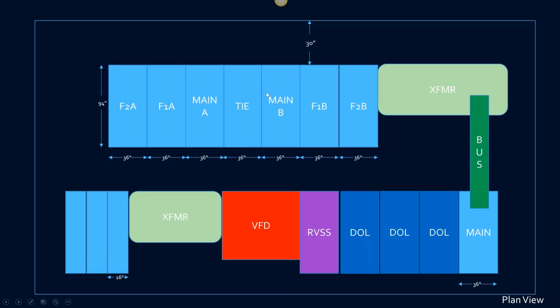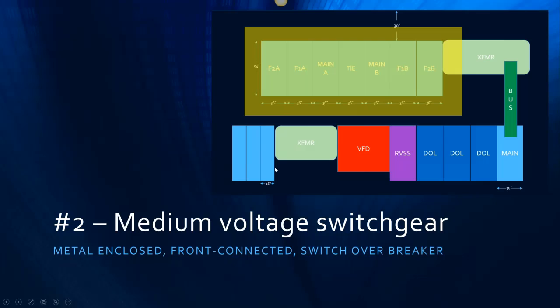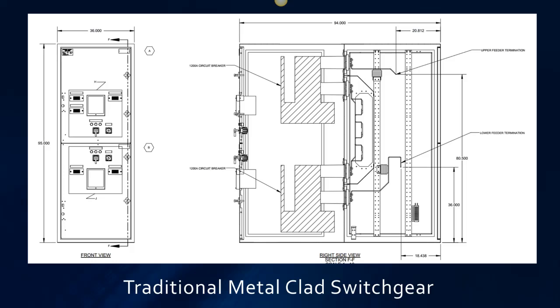So let's see what we've done to our room. We really have made some progress here. Over here down at the bottom left, we've converted this to 16-inch sections, and we still have our 3 load break switches. So moving on, the next item we're going to look at is the medium voltage switchgear. And there's lots of different options here. In the last 15 to 20 years, there has been some pretty good innovation in the world of medium voltage switchgear. At first, let's take a look at what is the old standby, which has been around forever, and this is what we call metal-clad switchgear.